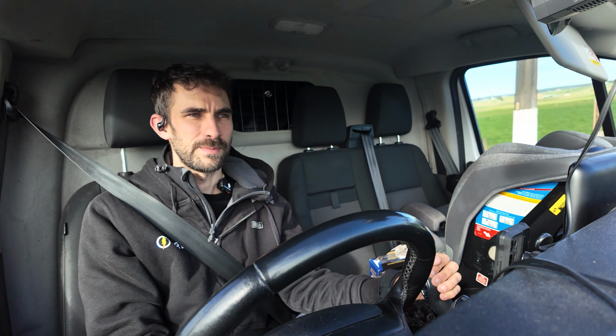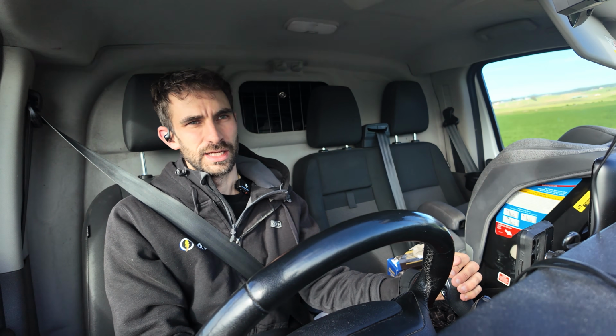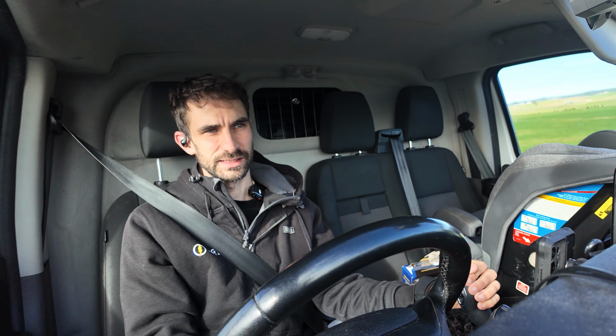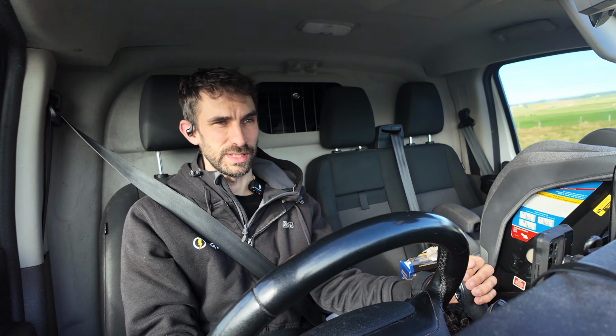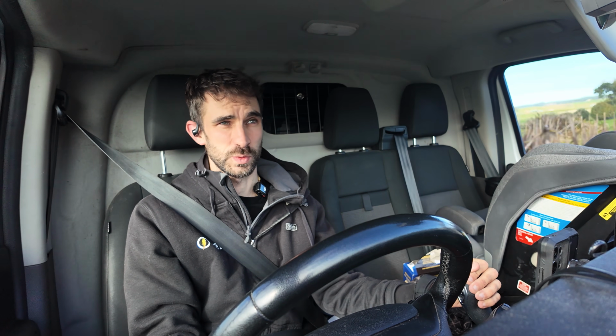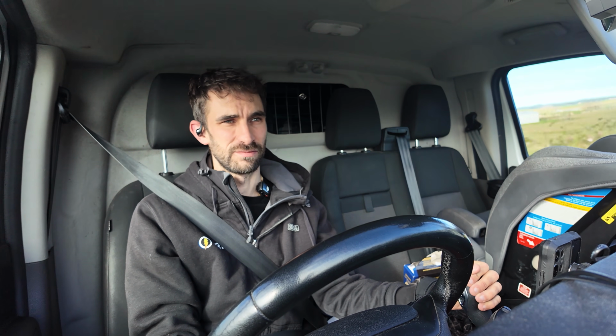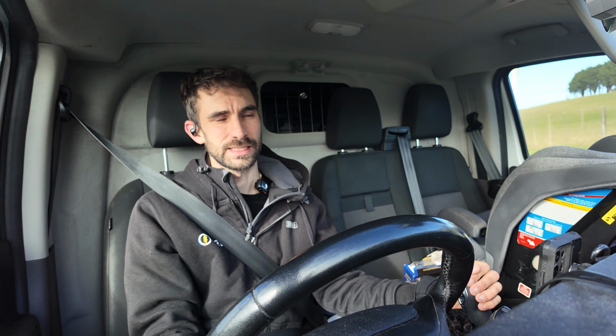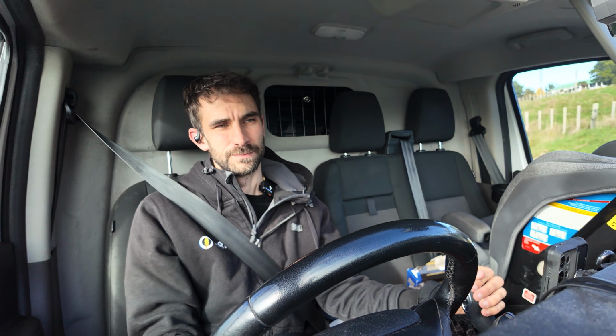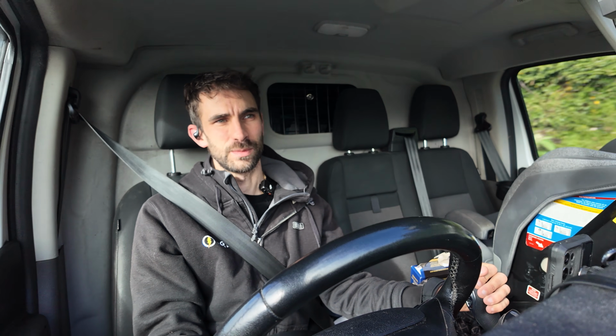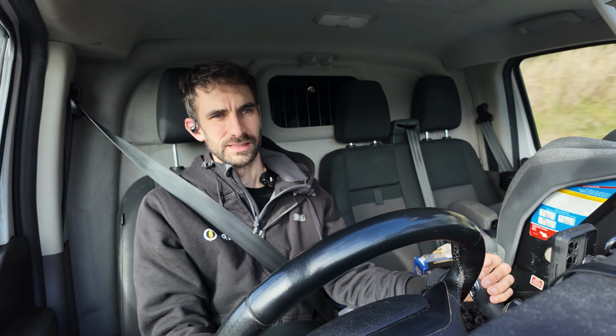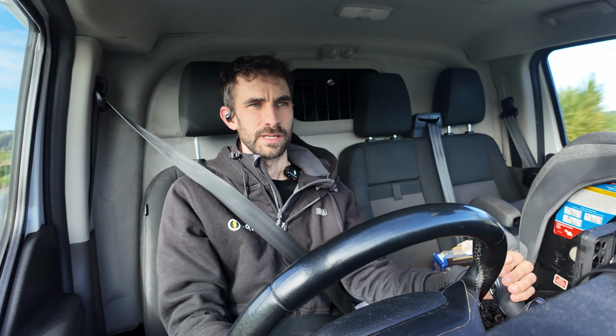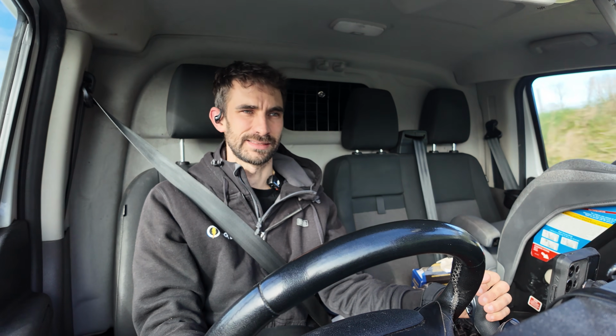Now back on the MEN system, the earthing system, like I said, used to be the pipes running between the houses, which worked really well. Not only did you get a really serious connection to the earth mass, but you had that connection to the neighboring neutral conductors if your one was lost. But now, just putting a rod in the ground, the connection you get is really bad. It's not enough to trip a breaker.